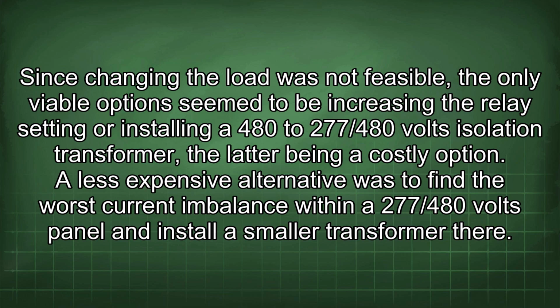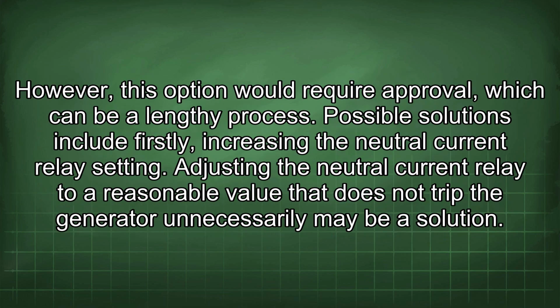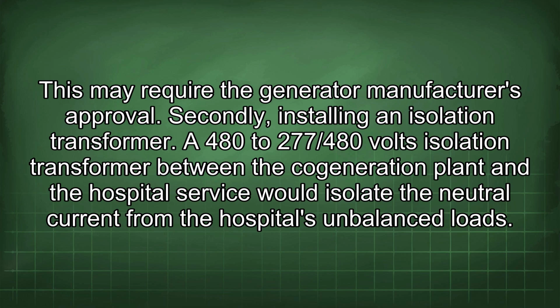A less expensive alternative was to find the worst current imbalance within a 277/480 volt panel and install a smaller transformer there. However, this option would require approval, which can be a lengthy process. Possible solutions include, firstly, increasing the neutral current relay setting. Adjusting the neutral current relay to a reasonable value that does not trip the generator unnecessarily may be a solution. This may require the generator manufacturer's approval.